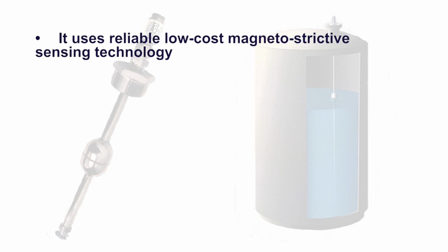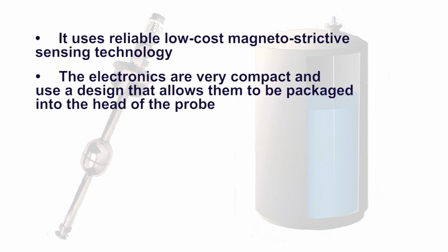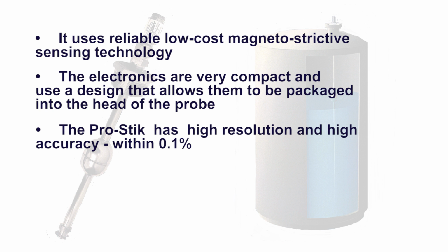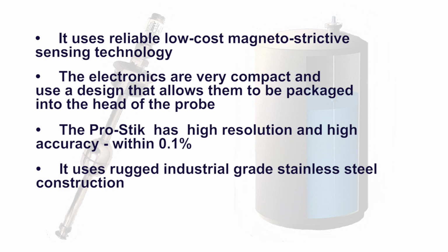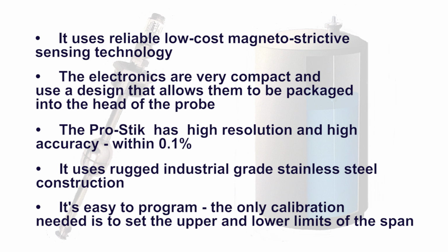The ProStik has the following key features. It uses reliable, low-cost magnetostrictive sensing technology. The electronics are very compact and use a design that allows them to be packaged into the head of the probe. The ProStik has high resolution and high accuracy, within 1/10 of 1%. It uses rugged, industrial-grade stainless steel construction, and it's easy to program. The only calibration needed is to set the upper and lower limits of the span.